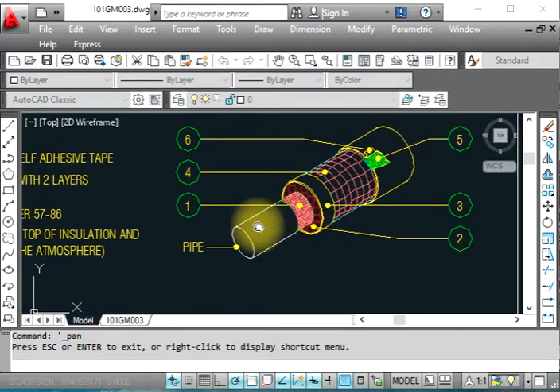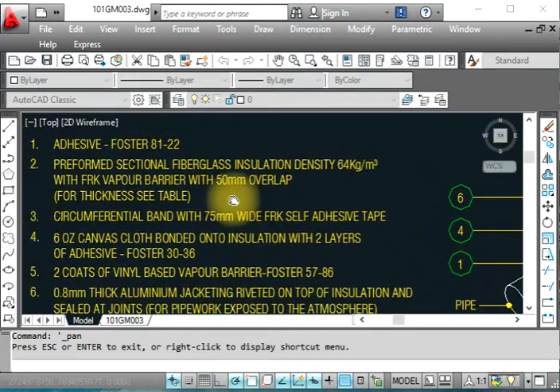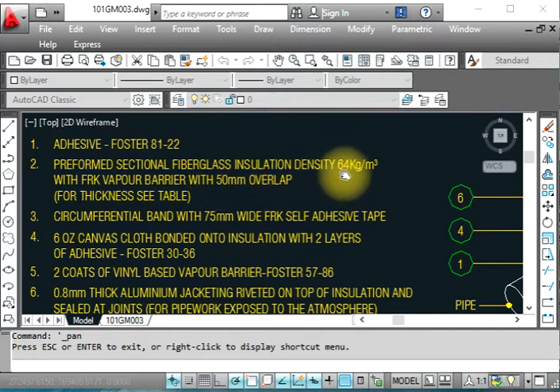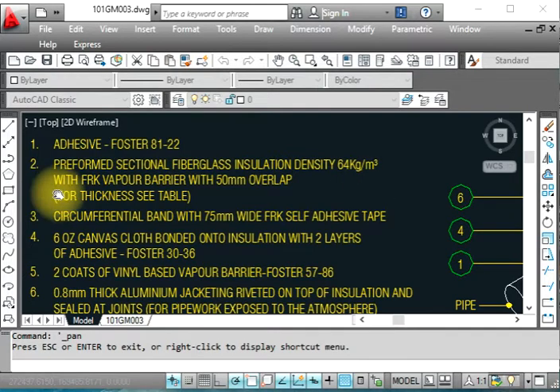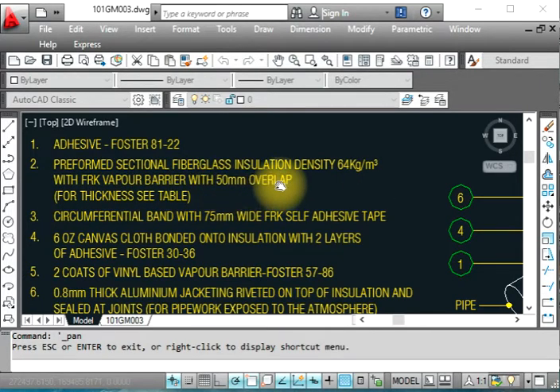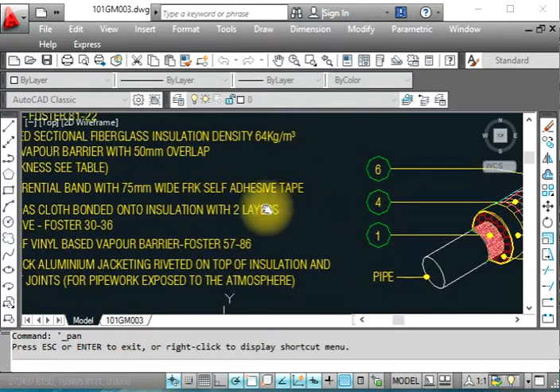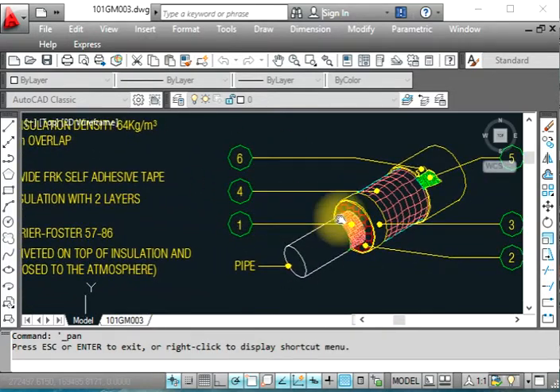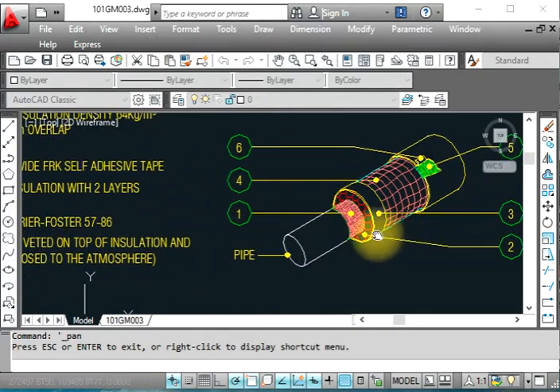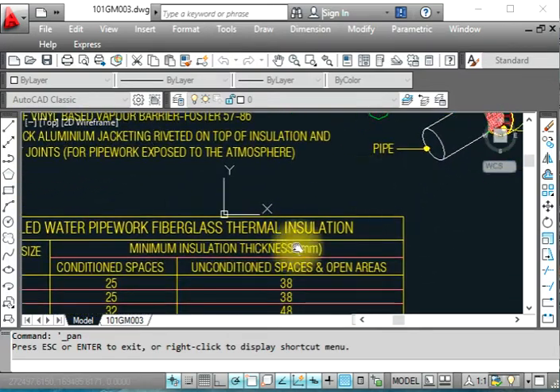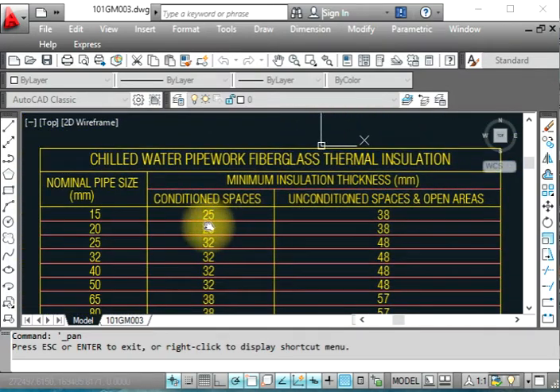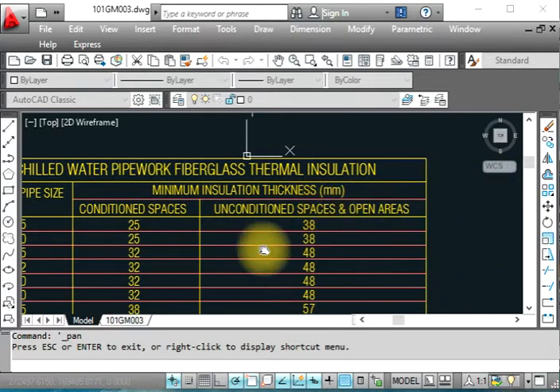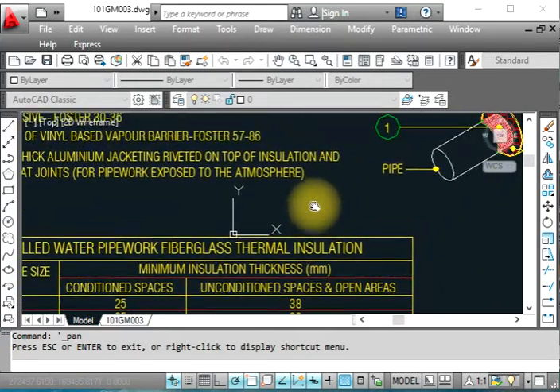The specifications show preformed sectional fiberglass insulation, density 64 kg per meter cube, with a FRK vapor barrier with 50 mm overlap. The thickness of insulation varies by pipe diameter and conditioned or unconditioned space. I will show you the table with pipe diameter and the condition of space.